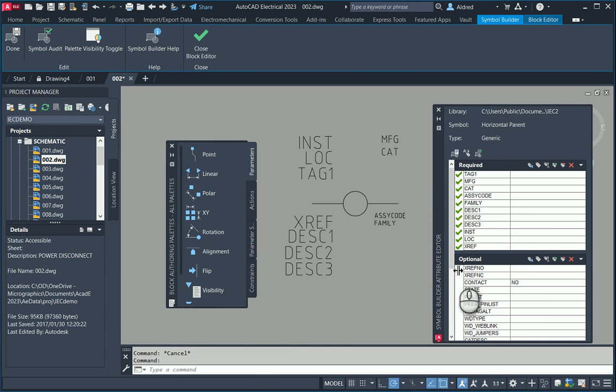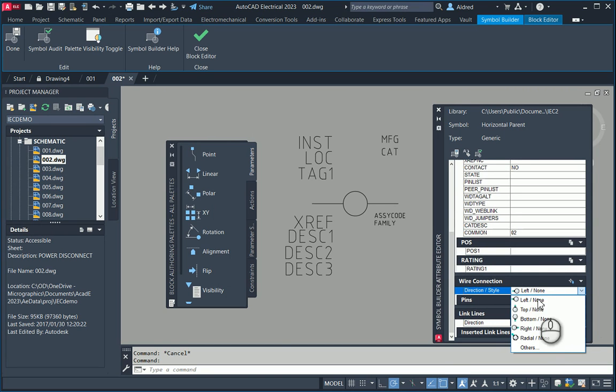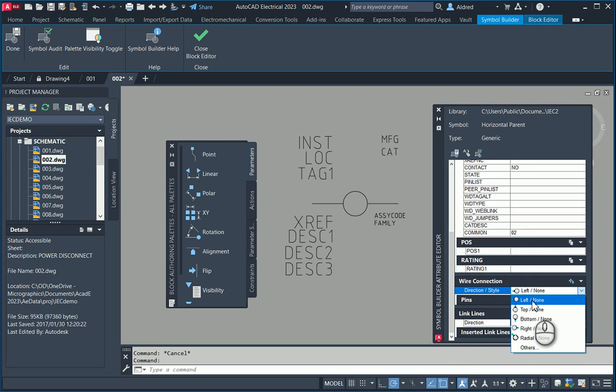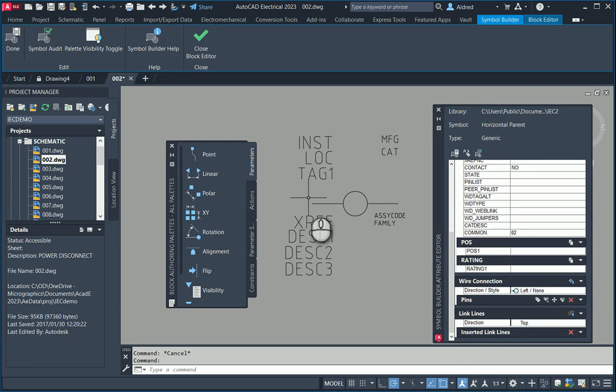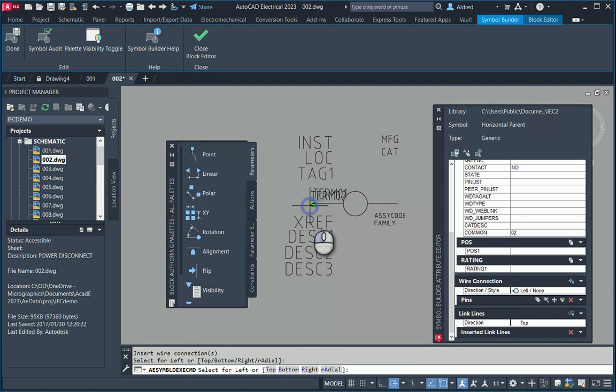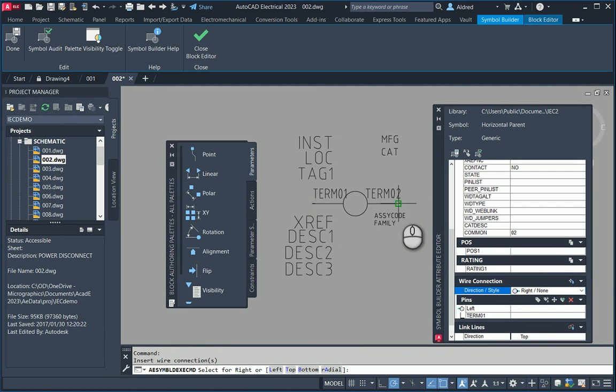With the insertion point, if I scroll down to the bottom, you'll see I've got my wire connection. With the wire connection, if I click on the drop-down, you'll see I've got left, top, bottom, right, radial. Because it's horizontal, I'm going to need left and right — this is where the wires are going to come into the symbol. I'll click on left, insert wire connection, select on the end points, then go to right, select insert, and select on the right-hand side.